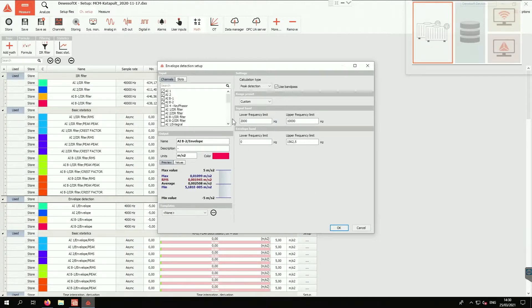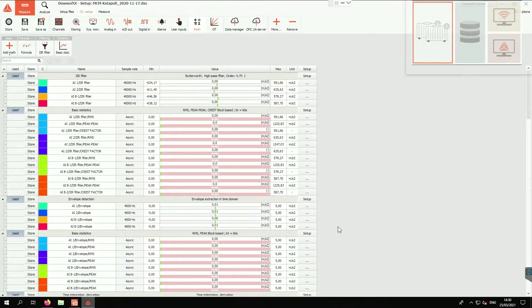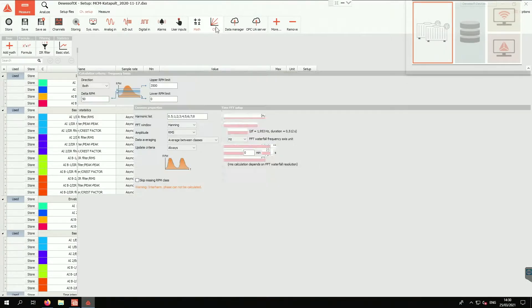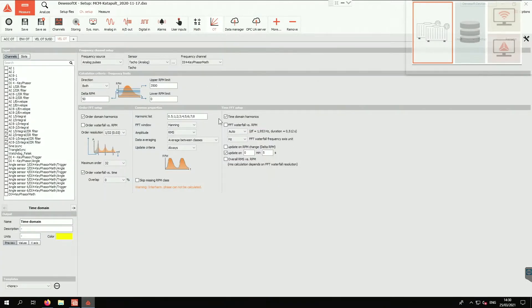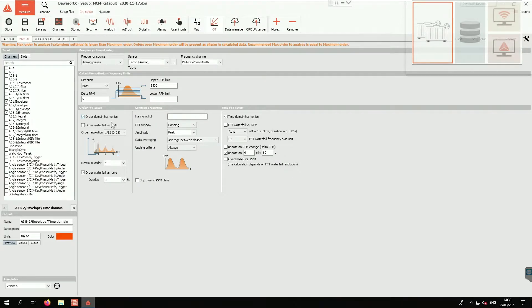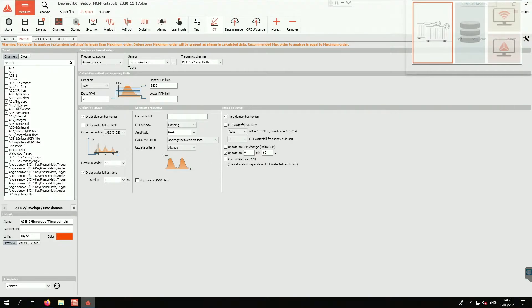This is the setup of the envelope. We also do the order tracking of the envelope because we want to have the data actually normalized to the RPM. If it changes, we want it to stay always the same. So if the RPM changes, we want to have the same looking FFT. That's why we use the order tracking.